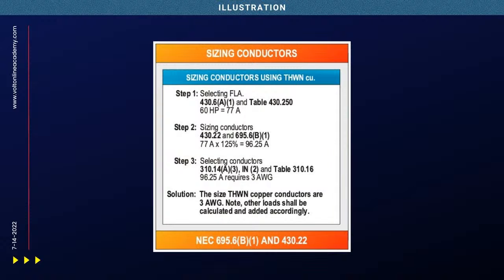When you look at 430.6(A)(1), when I'm sizing conductors or overcurrent devices, it tells you to go look at Tables 430.247 through 250. In this case, since it was three-phase, I'll look at Table 430.250, and for that 60 horsepower motor, it's going to tell you it's good at 77 amps. Now, when I size the conductors, 430.22 and 695.6(B) tie into each other. If I'm sizing the conductor to one motor, what do I take it at? 125%.